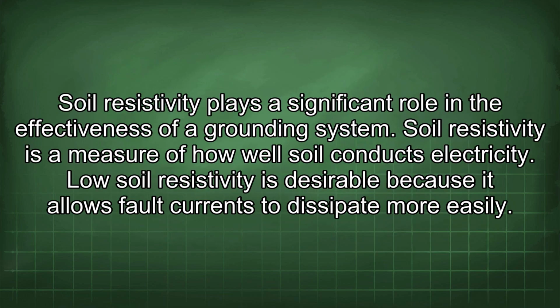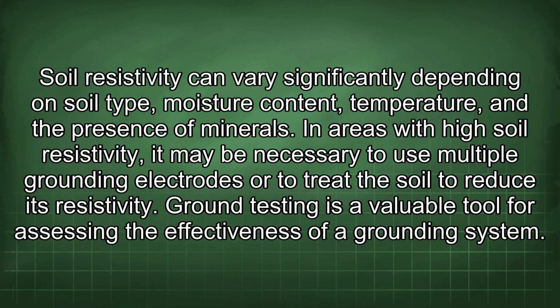Soil resistivity plays a significant role in the effectiveness of a grounding system. Soil resistivity is a measure of how well soil conducts electricity. Low soil resistivity is desirable because it allows fault currents to dissipate more easily. Soil resistivity can vary significantly depending on soil type, moisture content, temperature, and the presence of minerals. In areas with high soil resistivity, it may be necessary to use multiple grounding electrodes or to treat the soil to reduce its resistivity. Ground testing is a valuable tool for assessing the effectiveness of a grounding system.